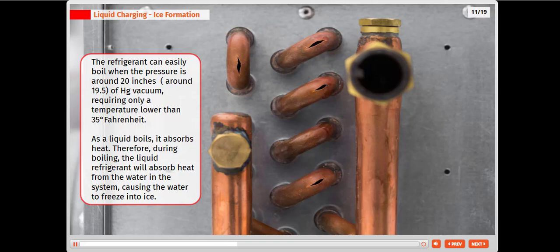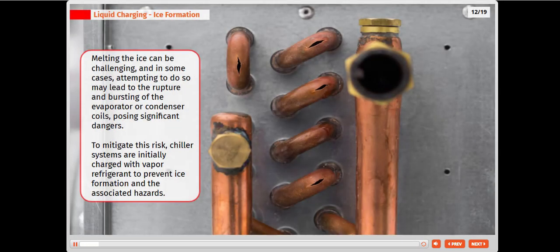As a liquid boils, it absorbs heat. Therefore, during boiling, the liquid refrigerant will absorb heat from the water in the system, causing the water to freeze into ice. Melting the ice can be challenging, and in some cases, attempting to do so may lead to the rupture and bursting of the evaporator or condenser coils, posing significant dangers. To mitigate this risk, chiller systems are initially charged with vapor refrigerant to prevent ice formation and the associated hazards.